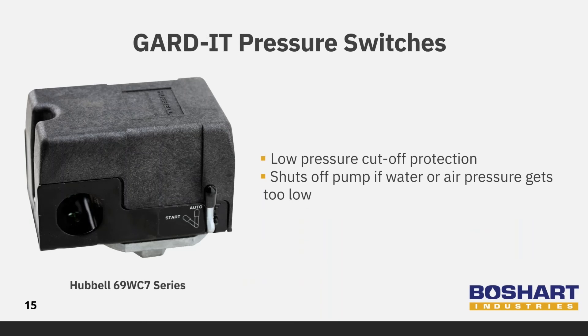Hubbell's GARD-IT pressure switch is wired in series with a conventional furnace pressure switch. It is designed to protect your water pump or air compressor motor by automatically shutting your pump off if water or air pressure gets too low. Once pressure returns to normal, you simply press the manual reset button to restart your system.